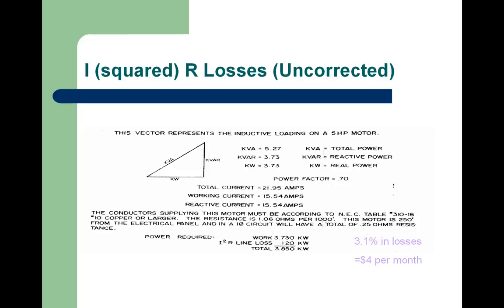Okay, the distributed energy through a facility would be what we're basically talking about, which is reducing load and the I squared R losses throughout a facility. If you're referring to generators, capacitors, power factor correction, and generators are not used a lot. There are issues with a leading power factor and generators with respect to voltage control. If anybody has any questions on that, they could go to powerfactorservices.ca and send me a note, and I could explain a little more on power factor correction with generators. I'm sorry if that didn't answer your question very well, but in any case, this may help a little bit in this particular one right here.